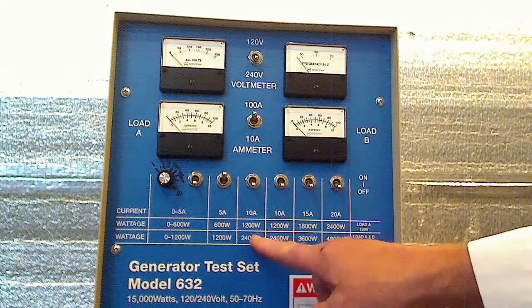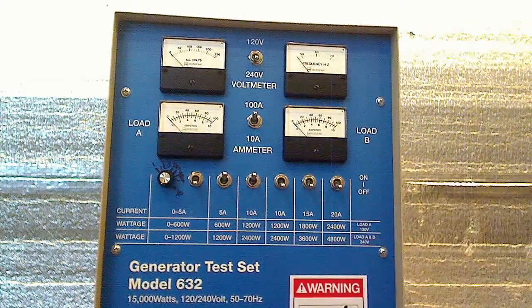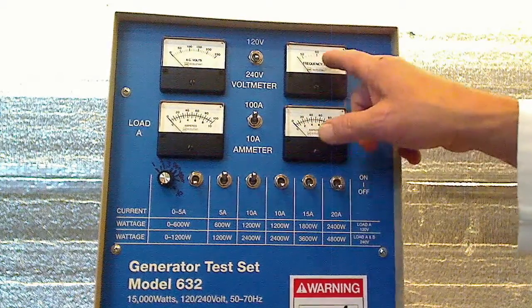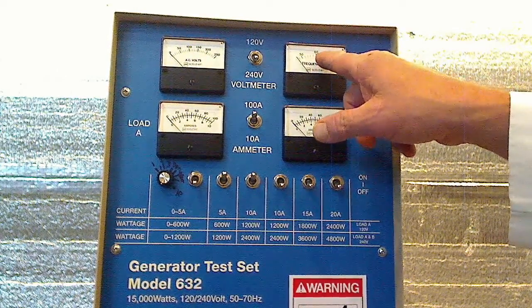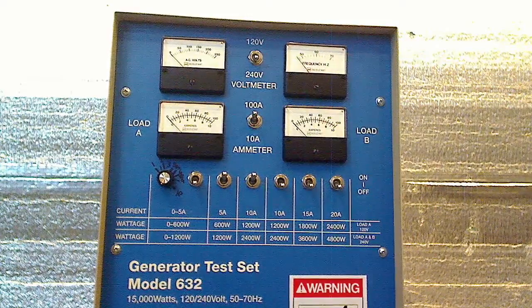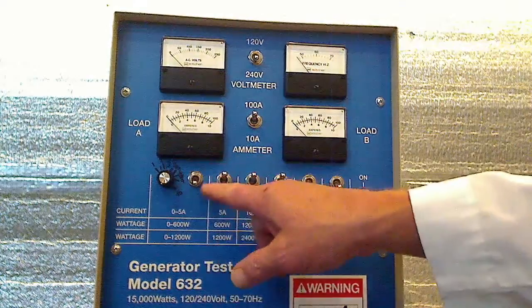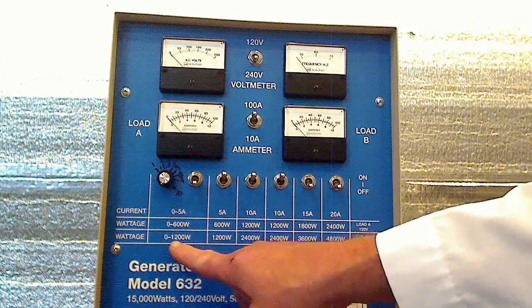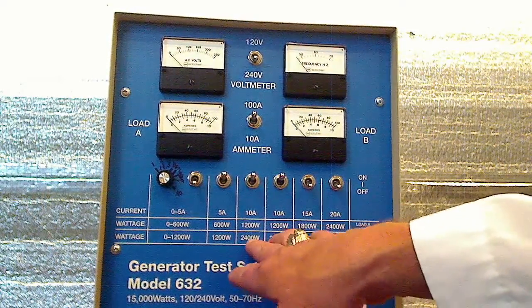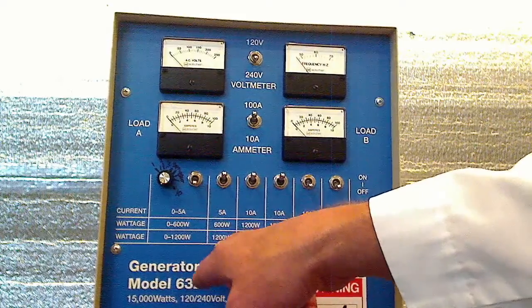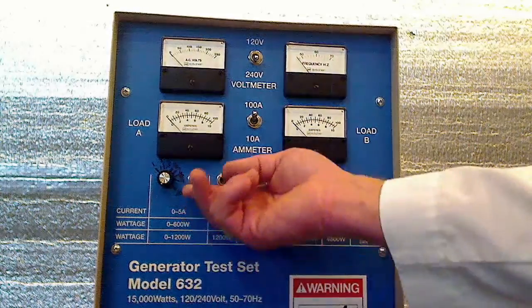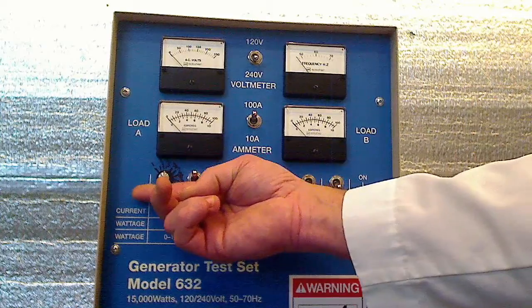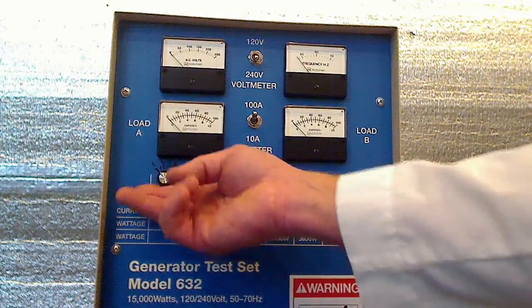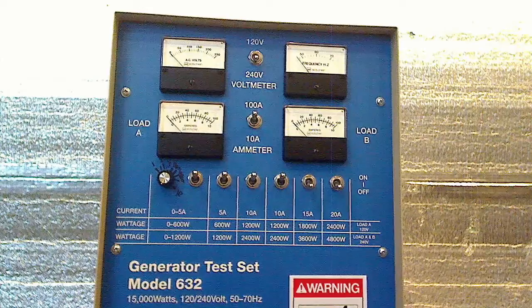Then we'll take it up incrementally, usually it doesn't change much but you can tweak it. We're always watching frequency on this, it's a beautiful feedback. Depending on the size of the generator, we go from there. Finally we have our adjustable load, which on this one goes up to 12. You can see 48 plus 12 is 6,000. So if you had a 66, you'd flip this on, 1, 2, 3, 4, 5, and you usually can't get past that on the 66. That's how we ramp up.